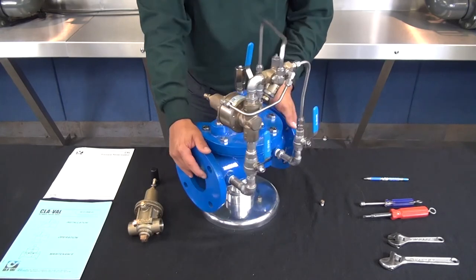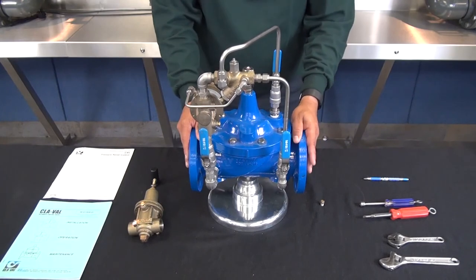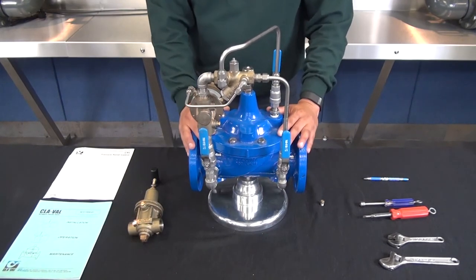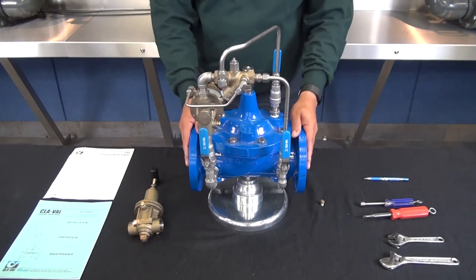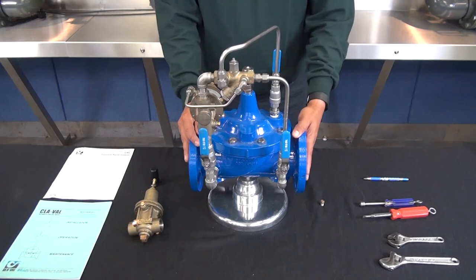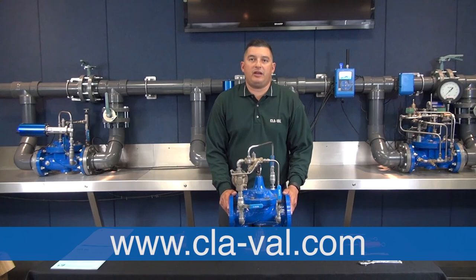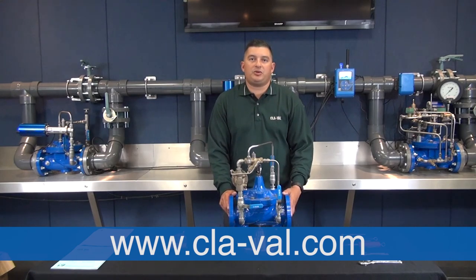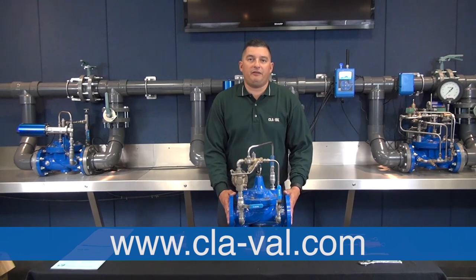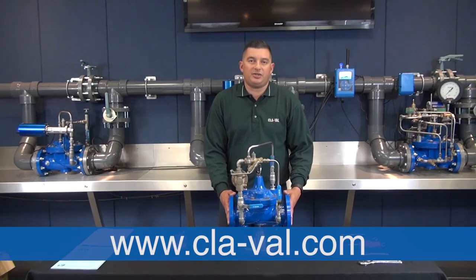It's important to exercise these valves as often as possible because in a relief valve application these valves are closed most of the time. We recommend inspecting both discs and replacing them if necessary. That concludes some of the basic troubleshooting procedures for our Cla-Val model 50-01 pressure relief valve. For additional videos or literature pertaining to the model 50-01 or our CRL pilots, please visit our website. Thanks for watching.